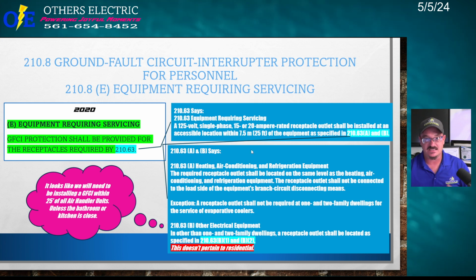So if you got a condensing unit, you better have a GFCI within 25 foot. Doesn't have to be dedicated. It can come off of any branch circuit inside the house. Doesn't say where it needs to get fed from. Doesn't say it needs to be a special dedicated branch circuit. But you need to have one. But it also says the heating equipment. So you now have to have a GFCI within 25 foot of the air handler on the inside.